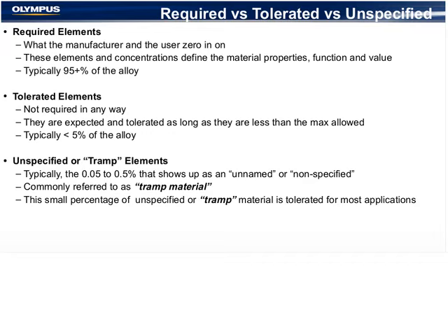Typically, these tolerated elements don't make up very much of the alloy, and they don't help very much in sorting versus other grades. The last type of element that I'll mention is an unspecified element or a tramp element, and virtually every kind of alloy has tramp elements in it. Our library gives you the ability to define to what level you would be willing to allow a tramp material to exist. So for common things like tungsten and cobalt and vanadium, which show up in stainless steels, you can put a max value in there and not let the fact that they're floating around at 0.07% create any sort of interference with grade identification.